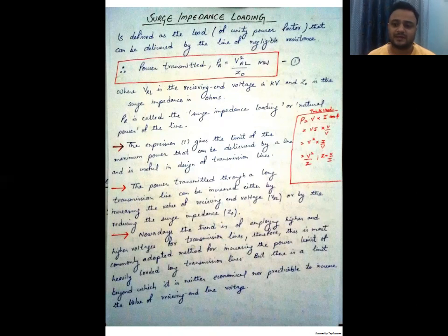So what do we get from this topic, why is it beneficial to us? The reason is that in a transmission line there is a parameter called maximum power that can be transmitted through the line. It is a very important aspect in the design of transmission lines. What is the value of the maximum power that can be transferred through a transmission line? That value can be calculated under the topic of surge impedance loading of a transmission line.